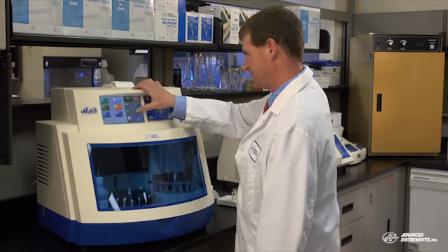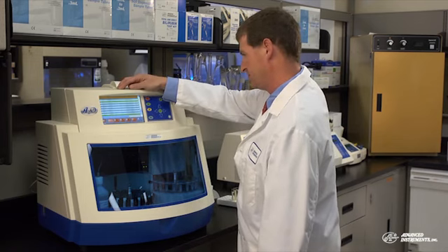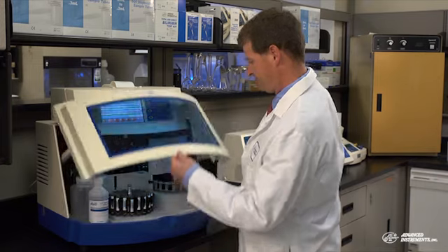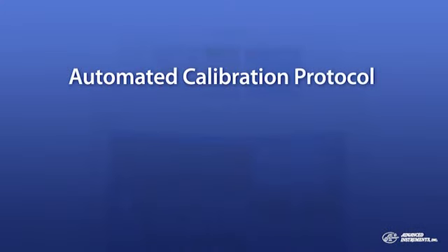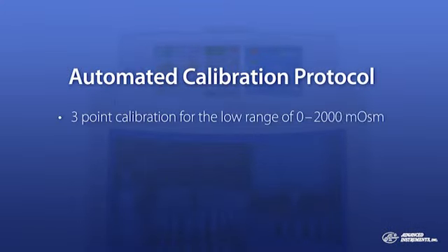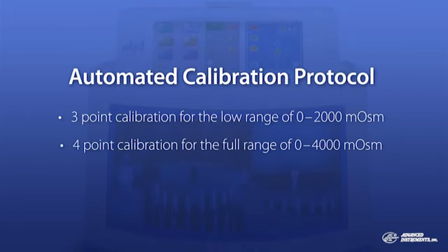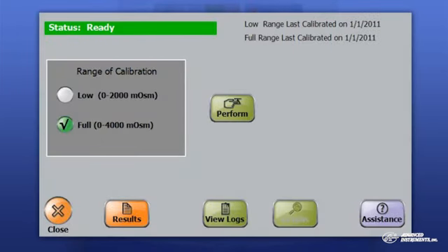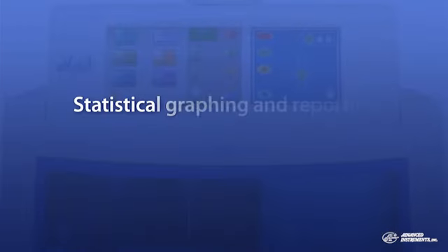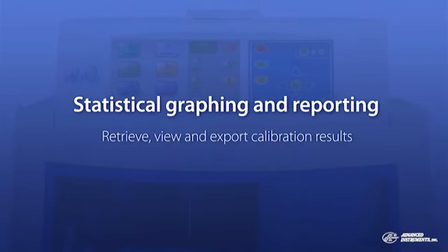Let's review the A2O advanced quality control features and capabilities. To ensure accurate results, the A2O features a fully automated calibration protocol that uses a 3-point calibration for the low range of 0 to 2000 milliosmoles and a 4-point calibration for the full range of 0 to 4000 milliosmoles. Statistical graphing and reporting capabilities make it easy to retrieve, view, and export calibration results.